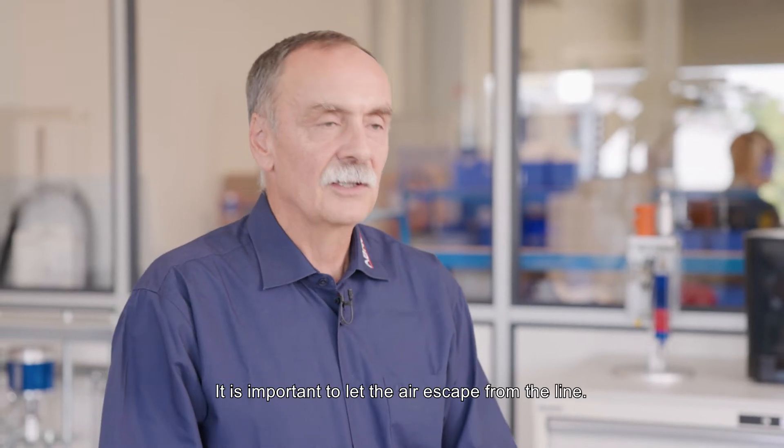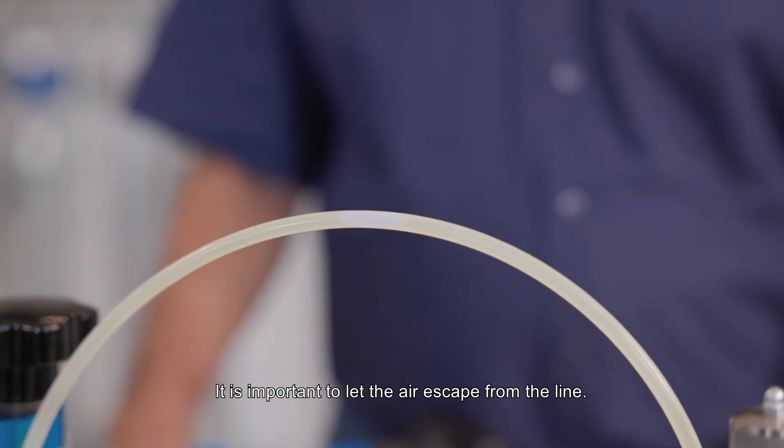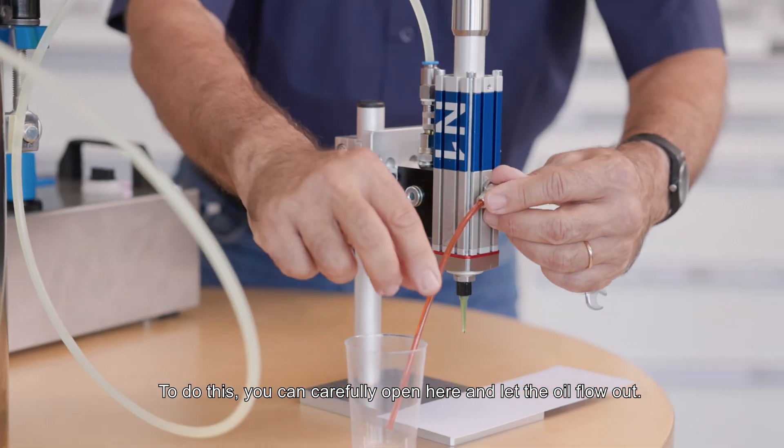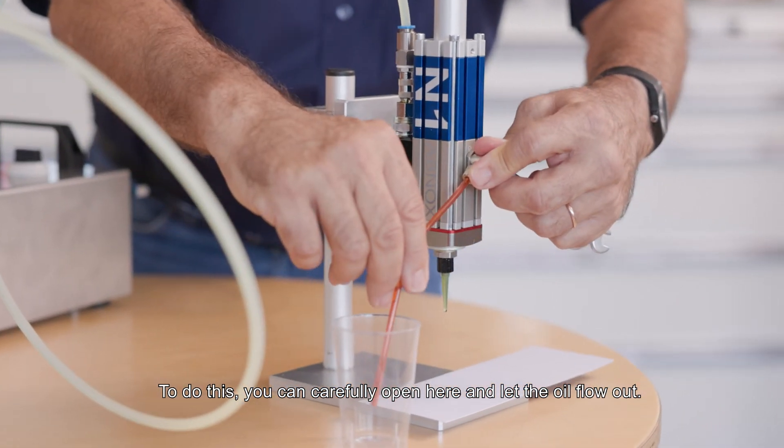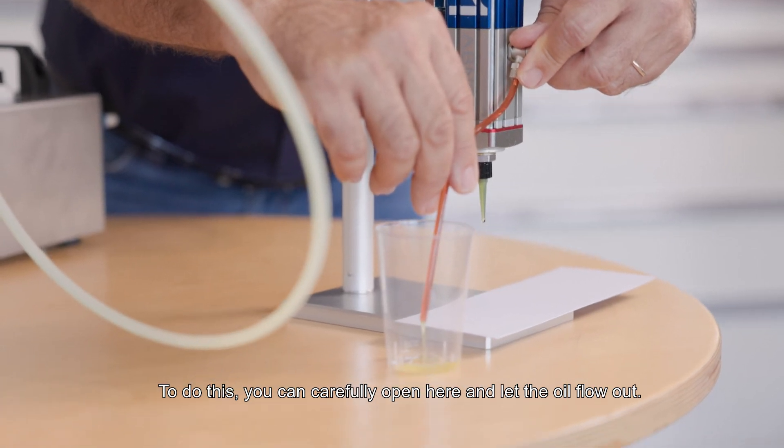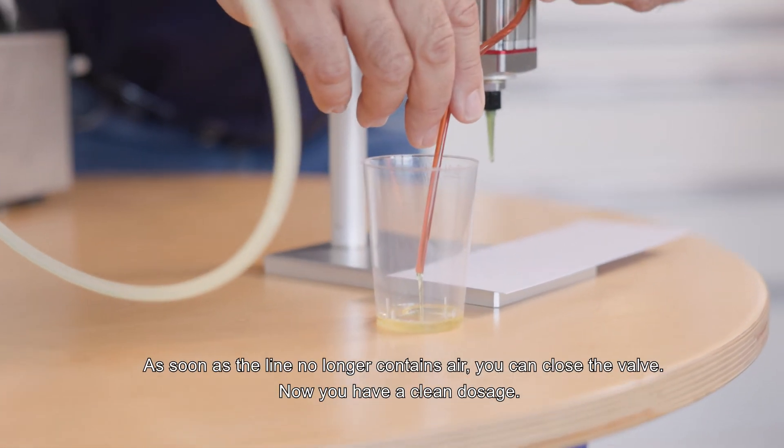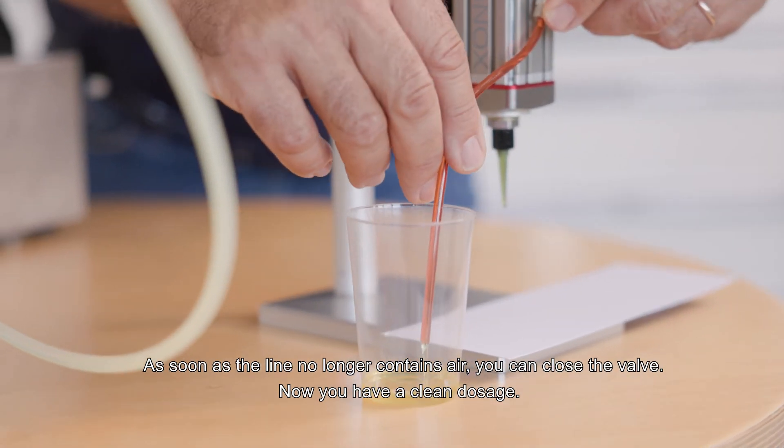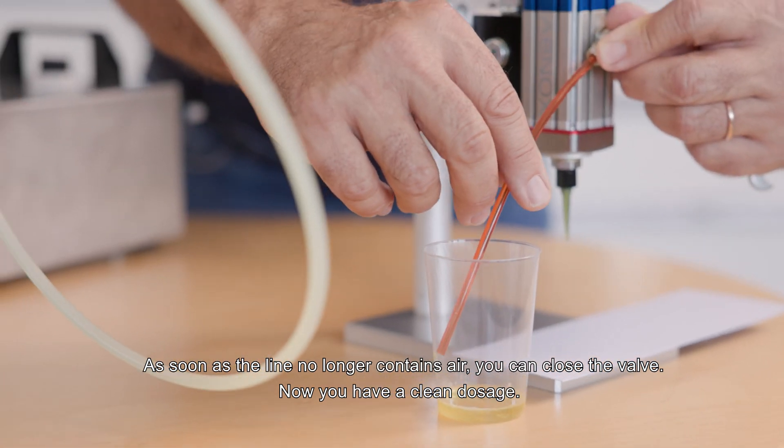It is important to let the air escape from the line. To do this, you can carefully open here and let the oil flow out. As soon as the line no longer contains air, you can close the valve. Now you have a clean dosage.